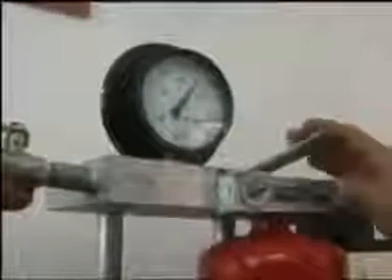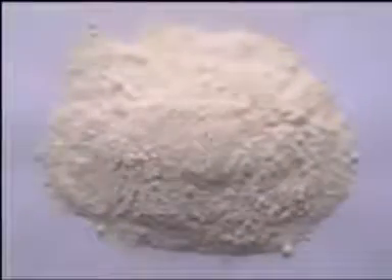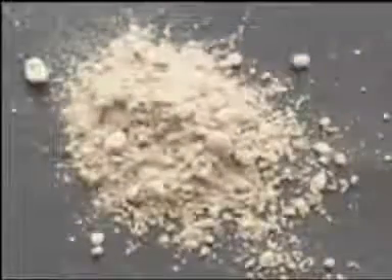Let's move on to the sourcing of the nitrogen propellant, the gas that drives the extinguishant out with a certain force. The critical factor here is purity. Low-grade nitrogen could introduce moisture into the extinguishant powder, causing it to cake and clog. All Indian manufacturers use commercial-grade nitrogen. Ceasefire uses high-grade nitrogen of a purity that prevents moisture entering the extinguishant.